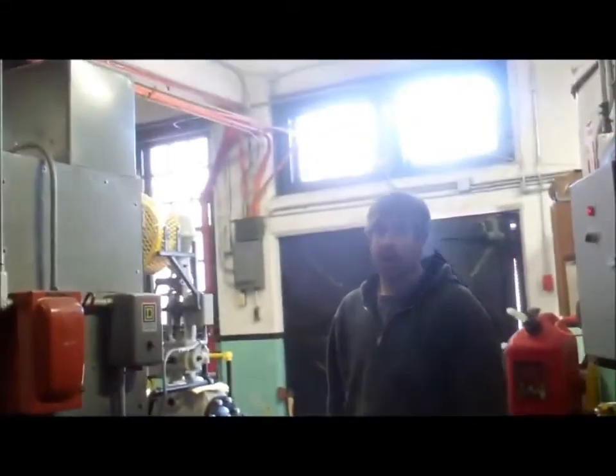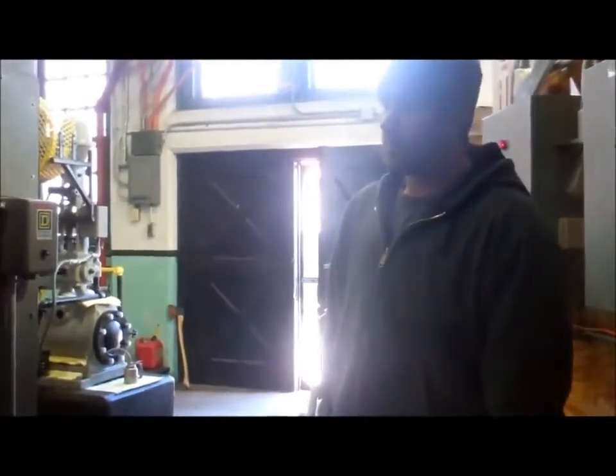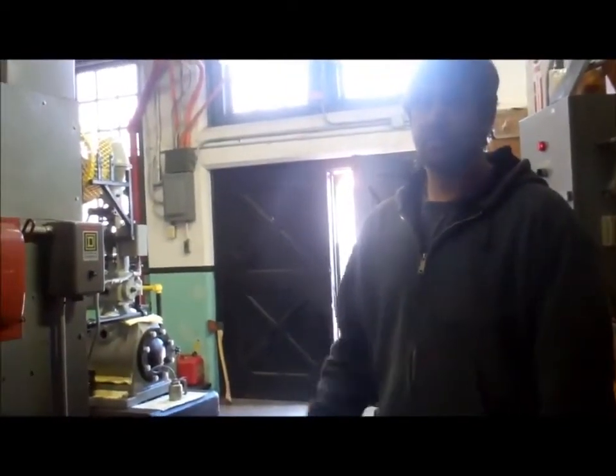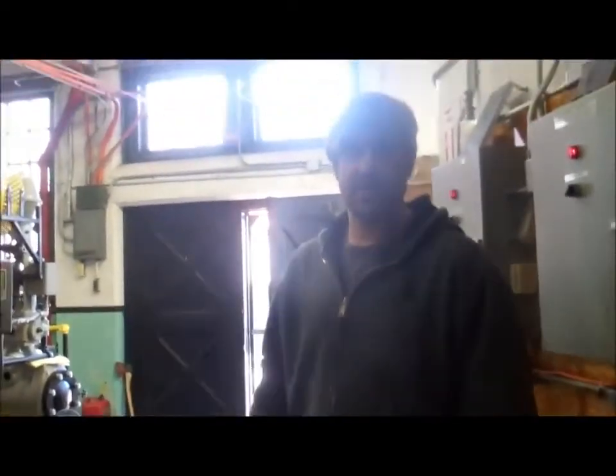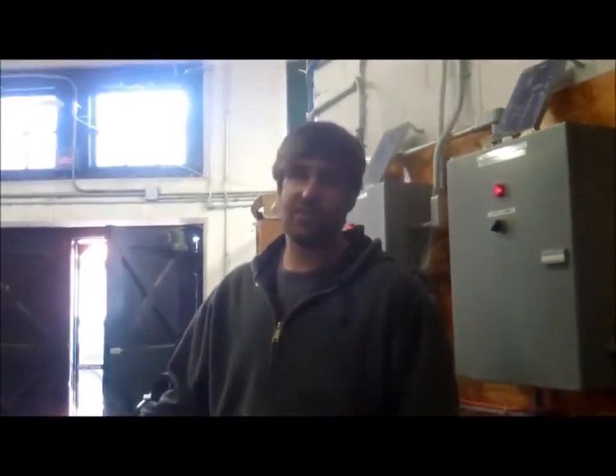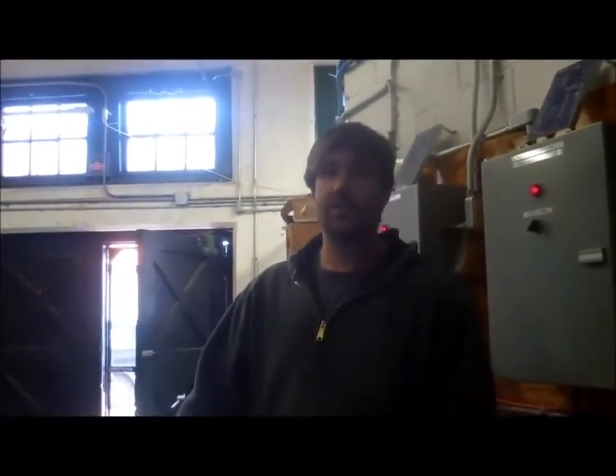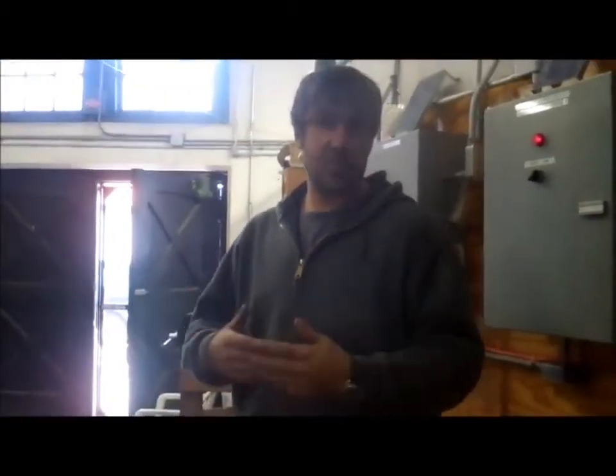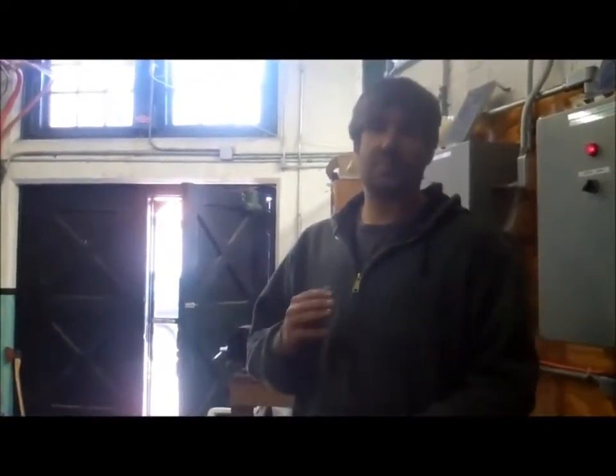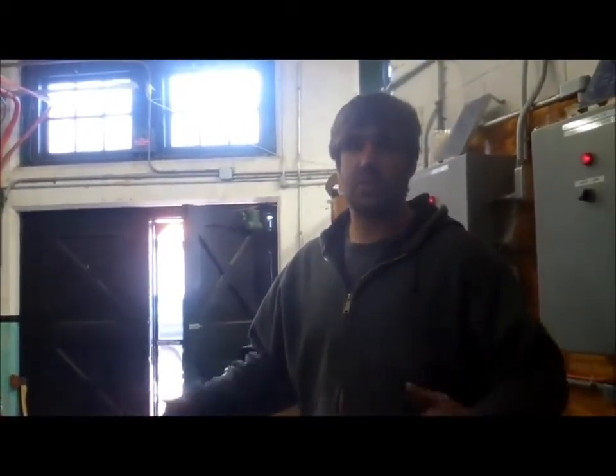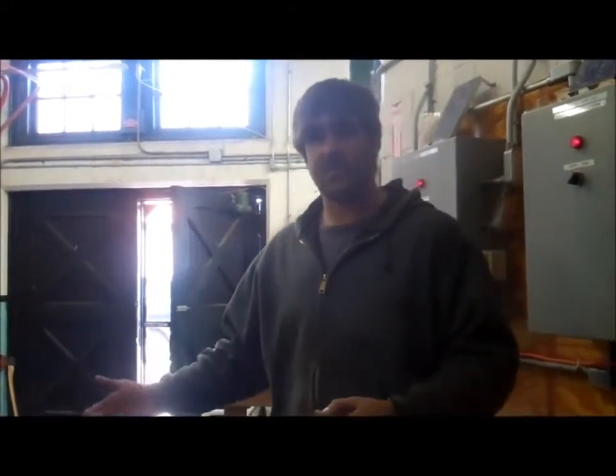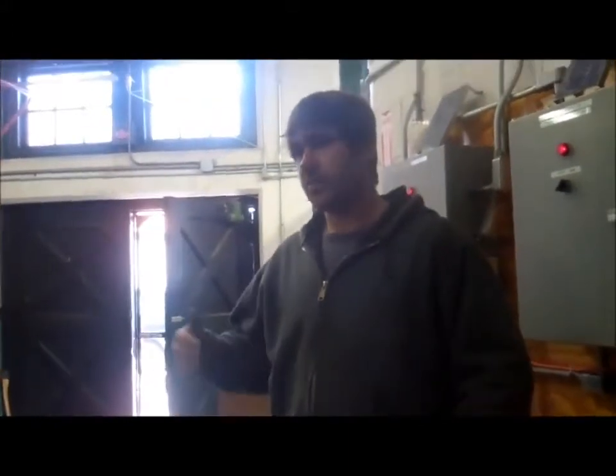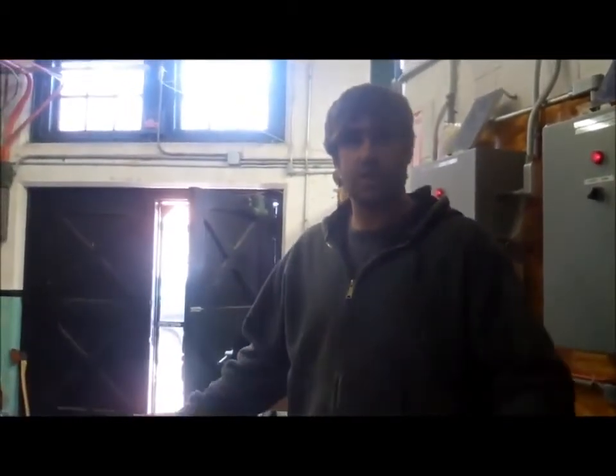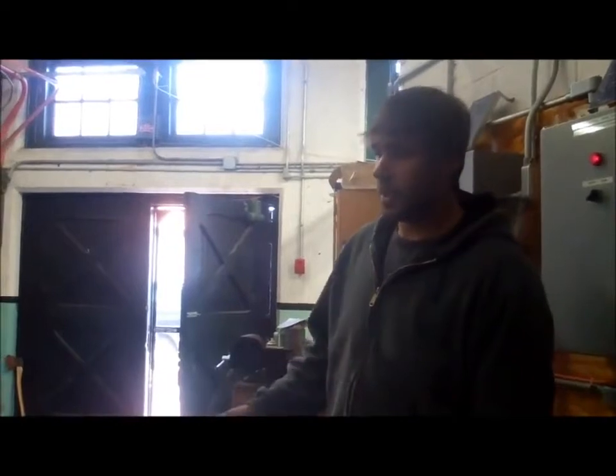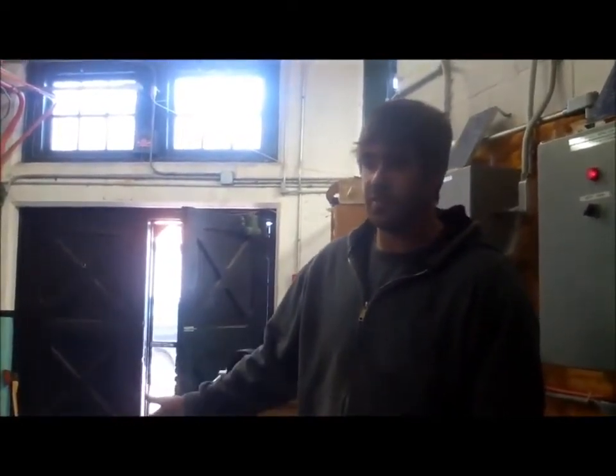So what happened, for example, did you have to go offline during the hurricane? No, but we sell our power on an ISO grid. It's a 5-minute basis, so it's just like the stock market, but it changes every 5 minutes. During emergencies like that, when there are so many power lines down and still so many people producing electricity, there's nowhere for the electricity to go. So they'll drop the price to 0. We're still producing electricity, but we're not getting paid. So it's an incentive for power plants to shut down. A lot of the larger power plants will actually turn off because you're not getting paid for your electricity, and there's wear and tear on machinery and stuff like that. So during the hurricane, for about a 12-hour period, we were still producing electricity, but we got 0 for it.